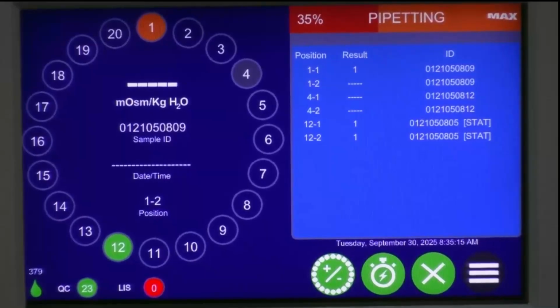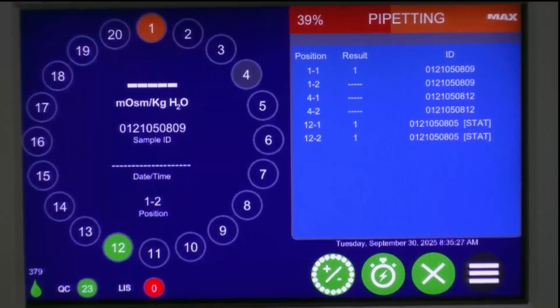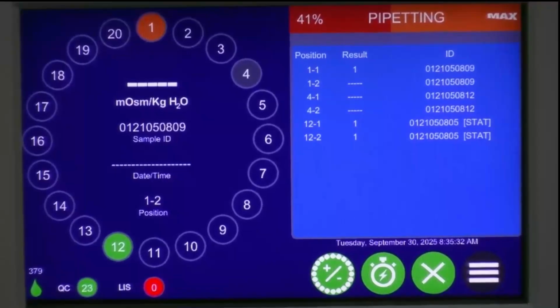It uses a different technology to freeze the sample after it's been supercooled really quickly, so we can get that freezing point plateau and take that measurement really accurately. So no more solenoid, no more need for maintenance on that impactor or solenoid. So yeah, that's another really great question.